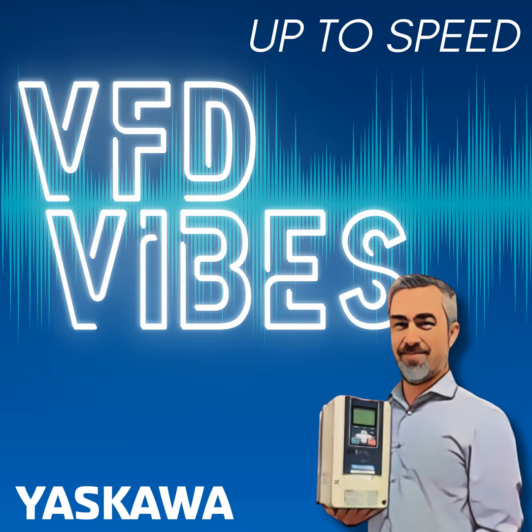The drive is looking for a 0 to 10 volt DC signal or a 4 to 20 milliamp signal. Now, that's how they're configured from the factory. But sometimes we have serial communication protocols, let's say BACnet on the HVAC side, maybe Ethernet IP on the industrial side, where we're sending those commands over the network. And if that were the case, you would have to reconfigure the run command and a speed reference. And these parameters may sound familiar: B102, Bravo 102 for your run command, and B101 for our speed reference. Great. That gets us running at the speed that our process needs us to be at.